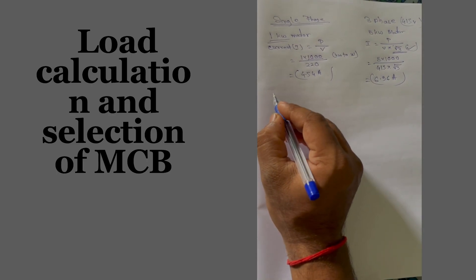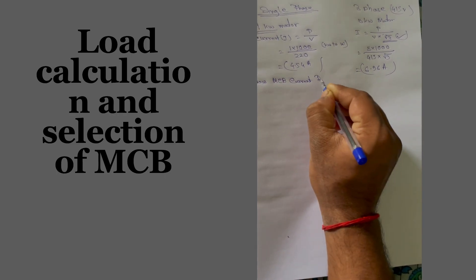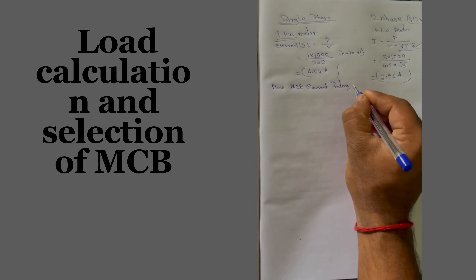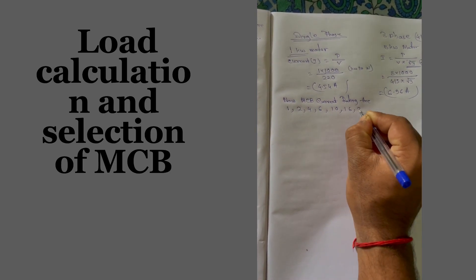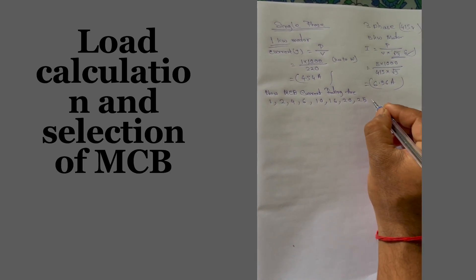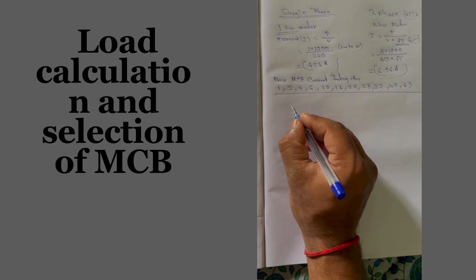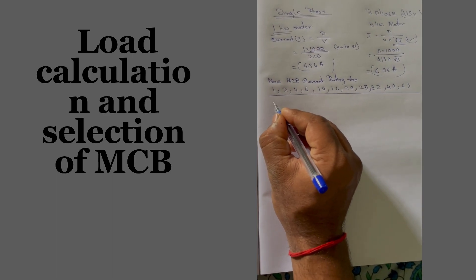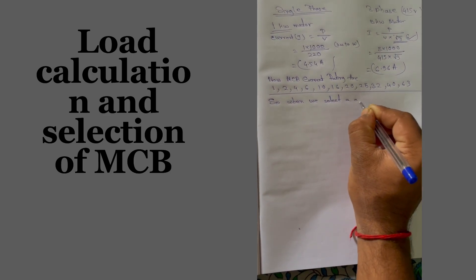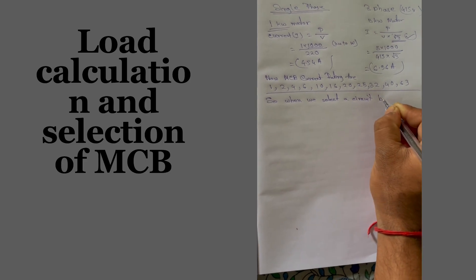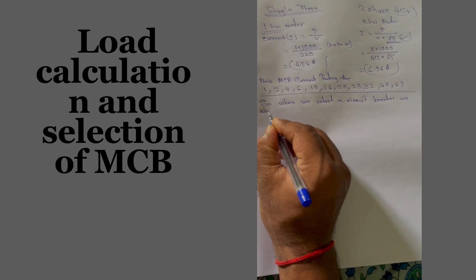Standard MCB current ratings are always specific values: 1, 2, 4, 6, 10, 16, 20, 25, 32, 40, and 63 amperes. When selecting a circuit breaker, we always choose 10 to 20 percent extra current rating above the calculated load current.